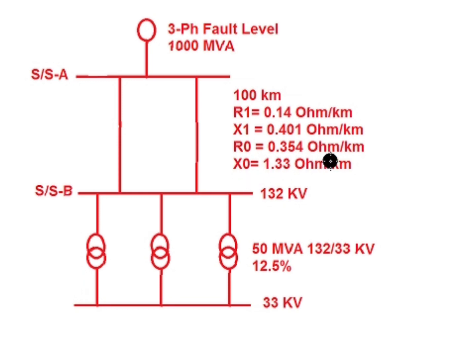The line parameters for the panther conductor are known: positive sequence resistance R1 is 0.14 ohm per kilometer and positive sequence reactance X1 is 0.401 ohm per kilometer. The zero sequence resistance is 0.354 ohm per kilometer and zero sequence reactance is 1.33 ohm per kilometer. Each transformer has a percentage impedance of 12.5 percent.